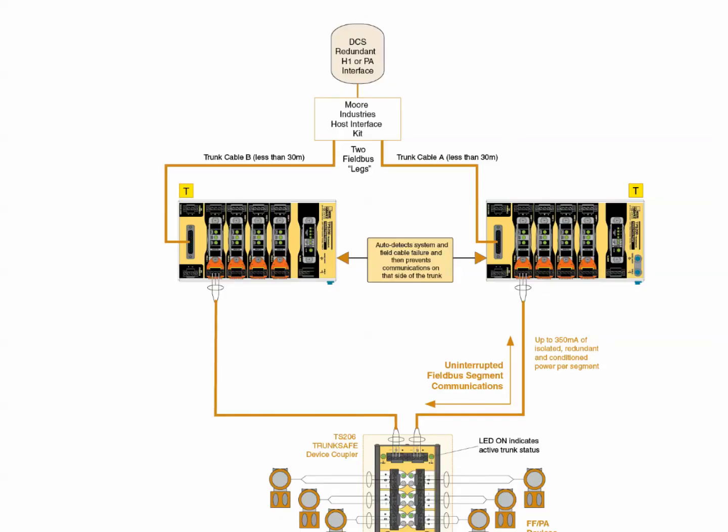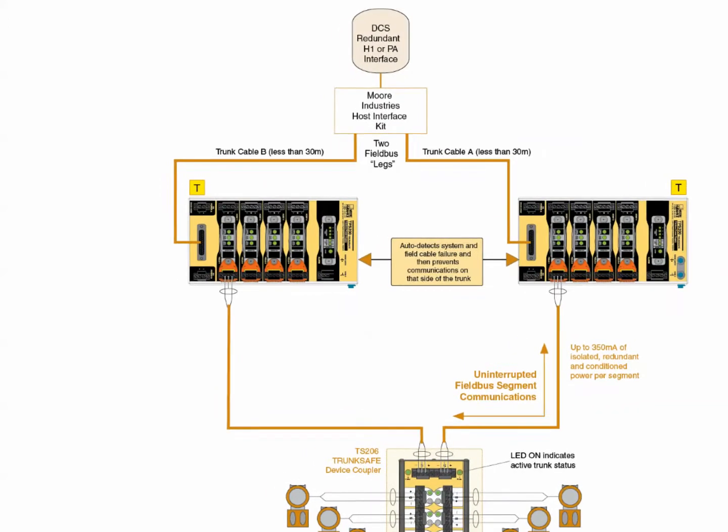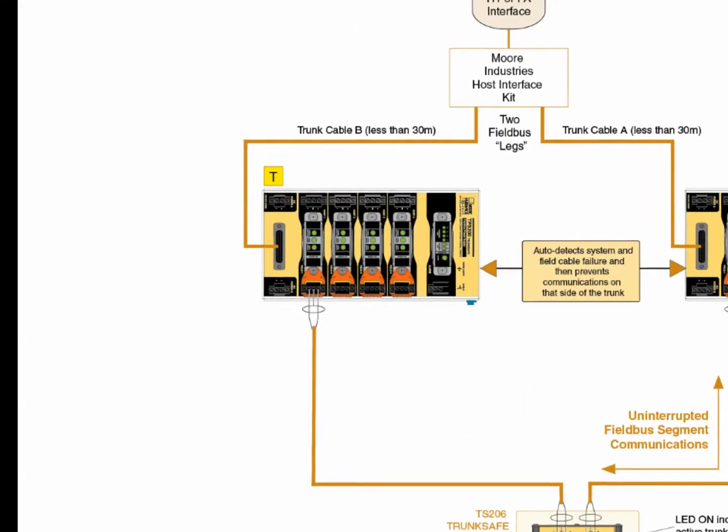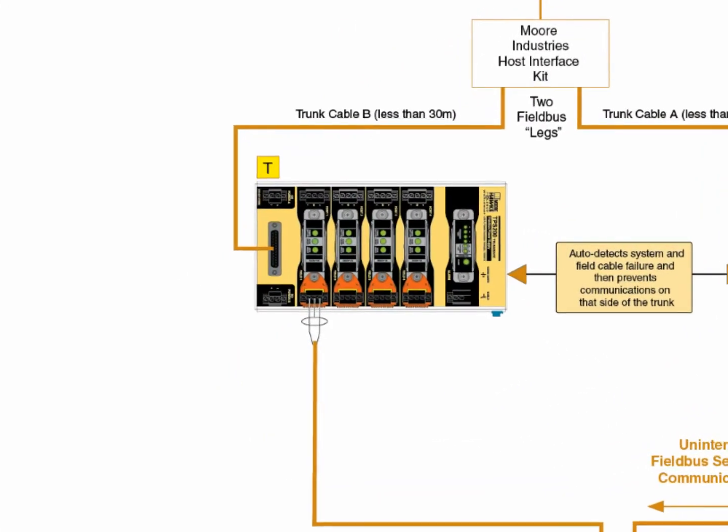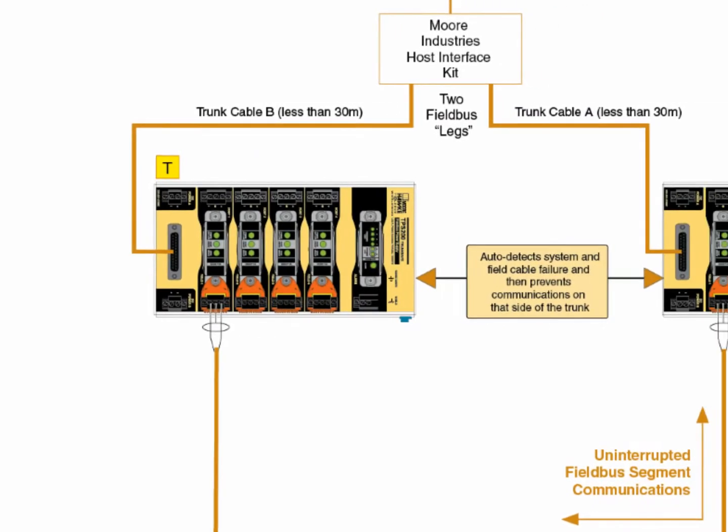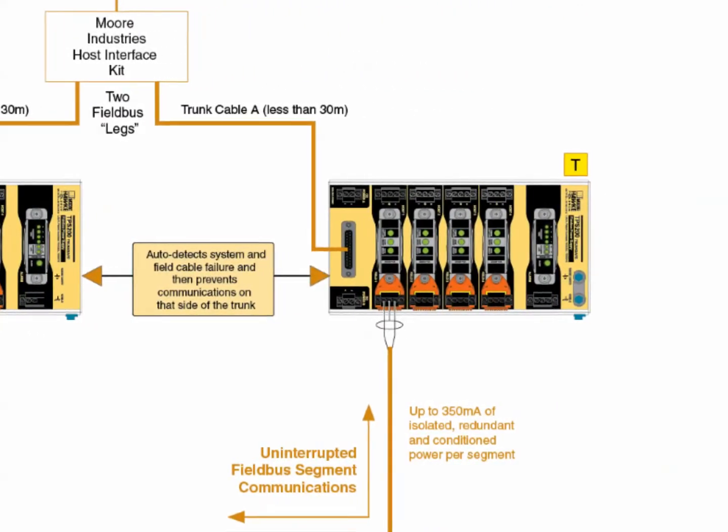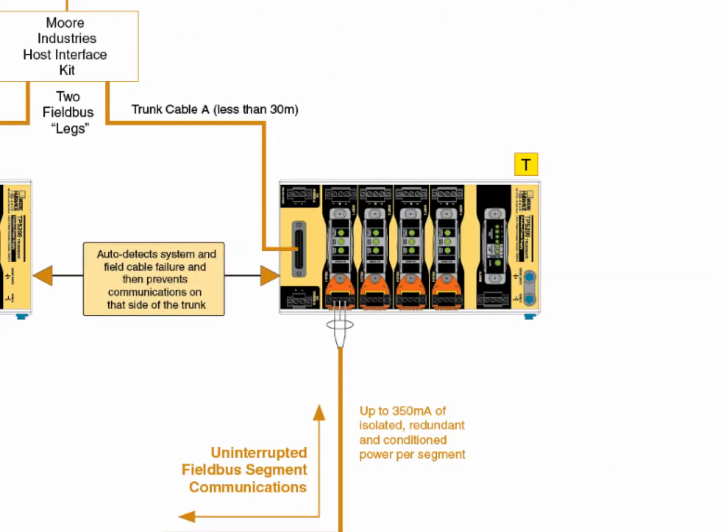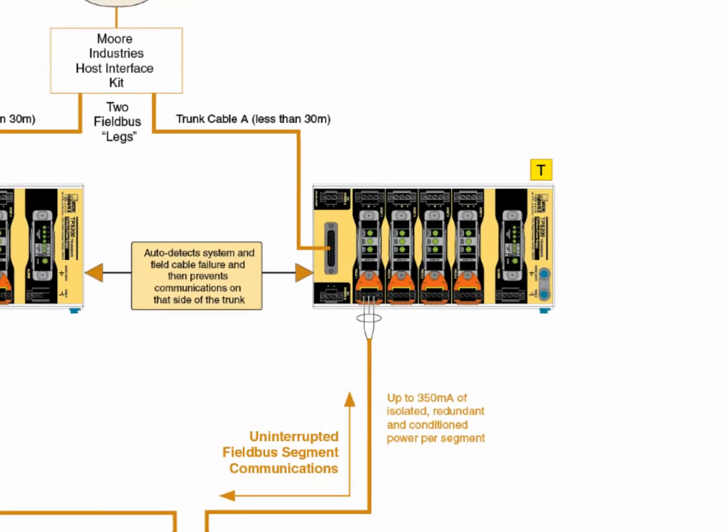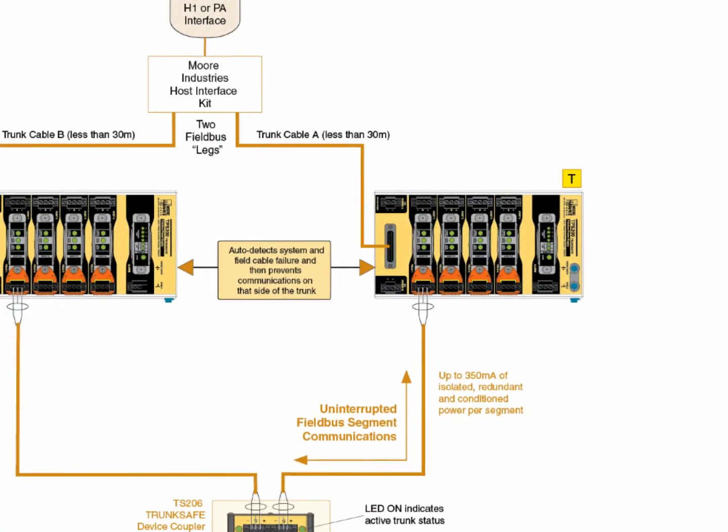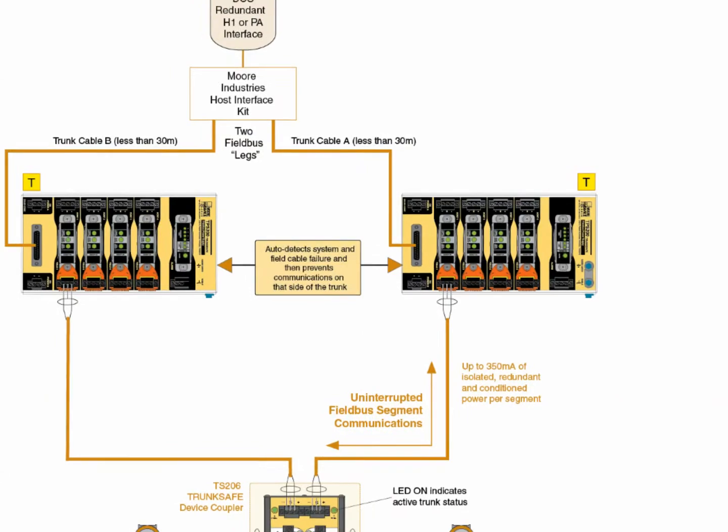Trunk Safe takes the single H1 or Profibus PA trunk output, regardless of the host system supplier, and converts it into two trunk outputs that are carried to the device coupler in the field. Each of these trunks pass through redundant power conditioner modules that provide conditioned power to the trunk and field-based device coupler.